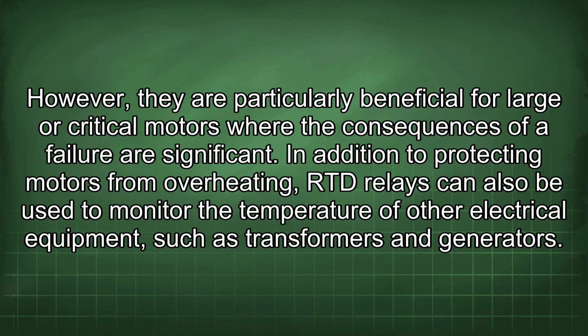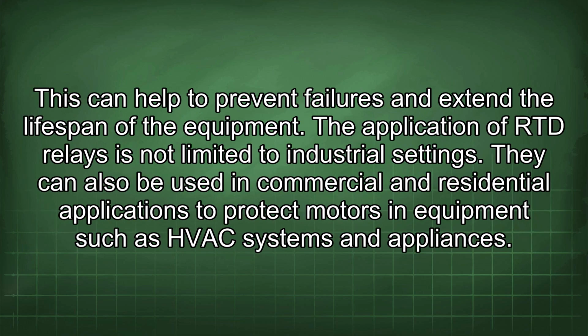In addition to protecting motors from overheating, RTD relays can also be used to monitor the temperature of other electrical equipment, such as transformers and generators. This can help to prevent failures and extend the lifespan of the equipment. The application of RTD relays is not limited to industrial settings. They can also be used in commercial and residential applications to protect motors in equipment such as HVAC systems and appliances.